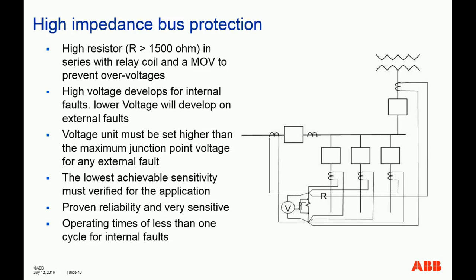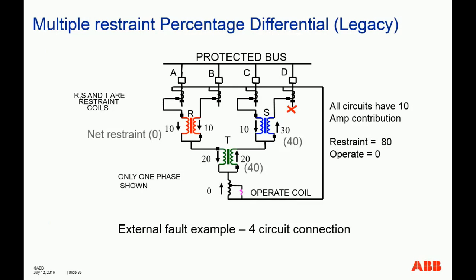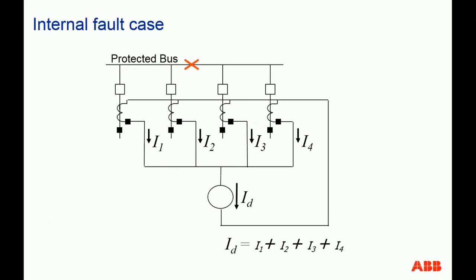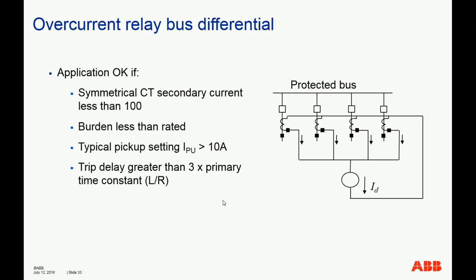How it works is, remember before, the very simple overcurrent type of relay connected in a differential way with all the CTs connected in parallel and brought to the relay coil. Imagine that the high impedance relay is nothing but exactly the same type of wiring, but with an extra big resistor, in this case over 1500 ohms, a very high resistive, very big resistor, in series with your operating coil, the relay coil. So why? Let's go back here.